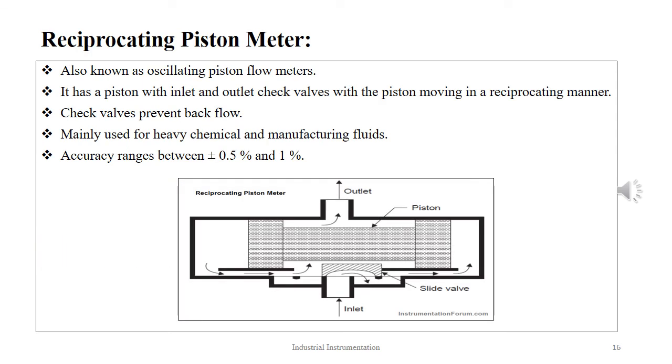The next type is the reciprocating piston meter. The reciprocating piston meter is also known as oscillating piston flow meter. It has a piston with inlet and outlet check valves with the piston moving in a reciprocating manner. The check valves prevent the backflow.